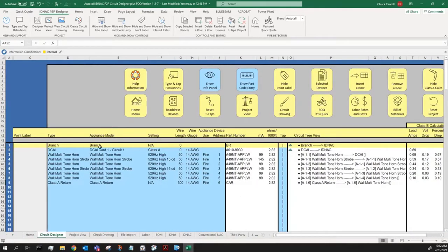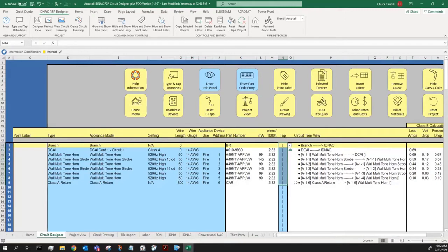So this is a simple Class A. Again, no T-tapping, straight line, just like we were doing for conventional devices. The difference is you have 29 volts instead of 24 as your starting point.